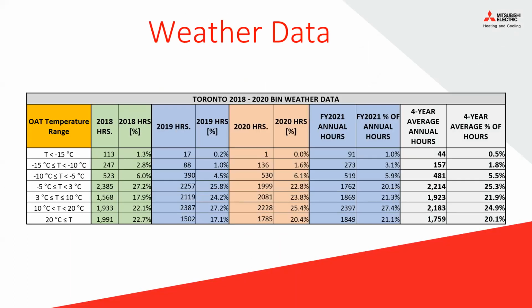So here's that weather data that I was mentioning before. This is a 3-year average of weather data in Toronto, and it shows that 98% of the year is spent above negative 15 degrees C. So if you size a system that can deliver 100% of the required capacity at negative 15 C, you're still above a COP of 1.5. And that's 50% better than the next alternative.